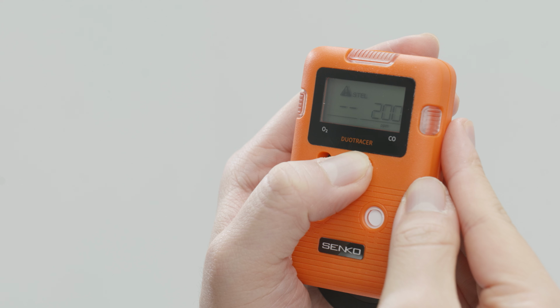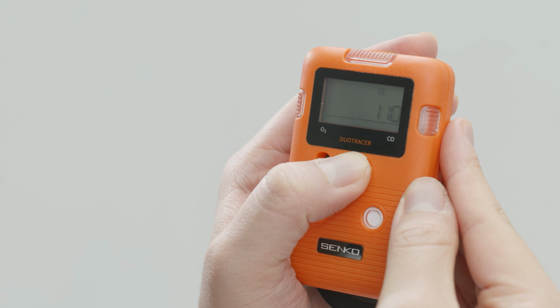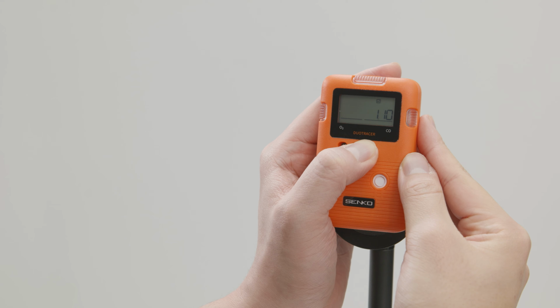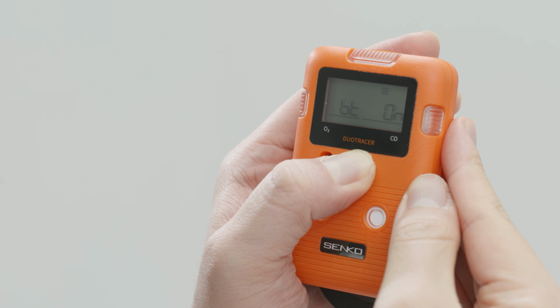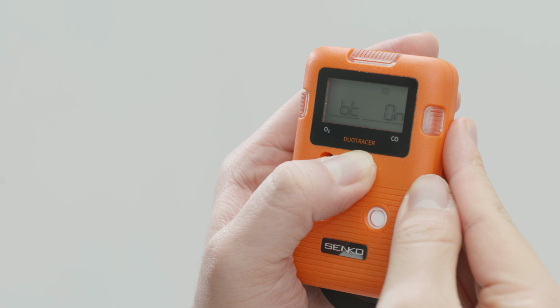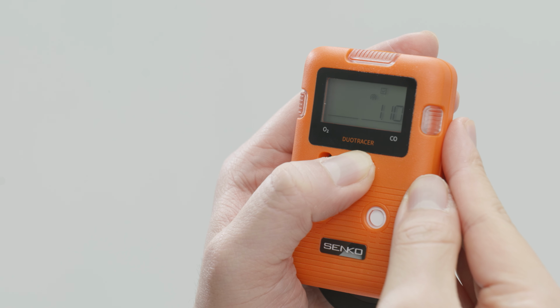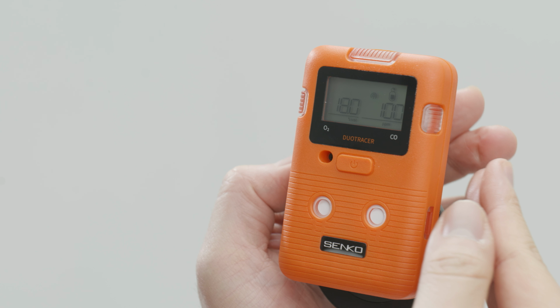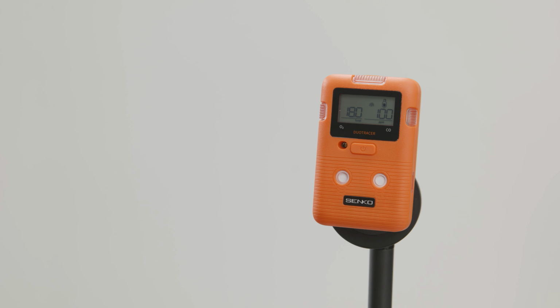Now, when the item you want is displayed on the screen, just press and hold the button to enter the detailed setting mode for that item. For example, when you're on the firmware version screen, a long press takes you to the wireless settings menu where you can turn Bluetooth on or off. And when you're on the correction concentration screen for each gas, press and hold the button to enter correction mode and proceed with either span or zero calibration. If there's no input for a certain period of time, the device will automatically return to measurement mode on its own.